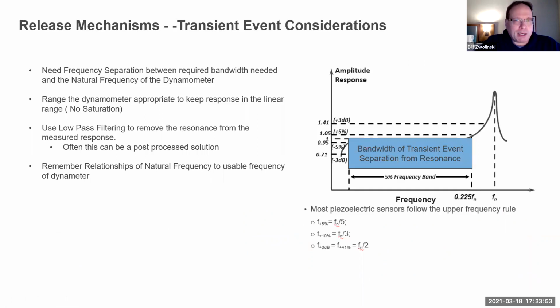With transient events, always keep in mind you need the right measurement capability. If you have an event and use that 1 over duration rule, say 1 over 1 millisecond is 1 kilohertz, and the natural frequency of your measurement system is less than 1 kilohertz, the resonance of the measurement system gets buried into the trace of what you're trying to measure. So it's tricky to measure transient events with force sensors - you have to understand the duration and characteristic of the event, and critically examine your force measurement system to get the maximum frequency out, so you get separation between the event duration and the resonance. It's one of the more challenging problems.